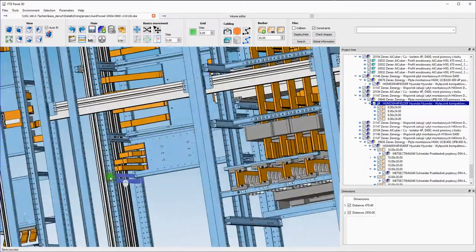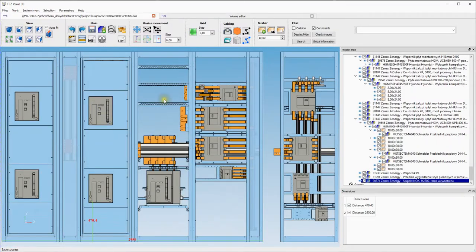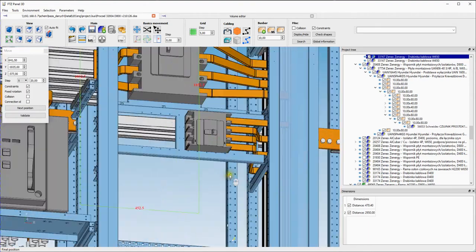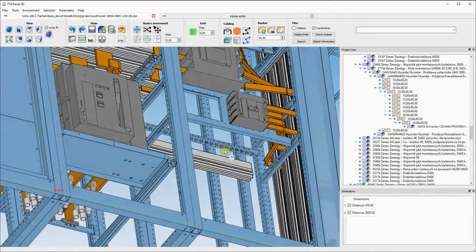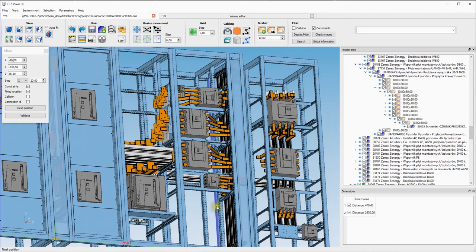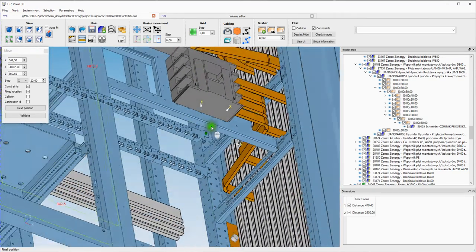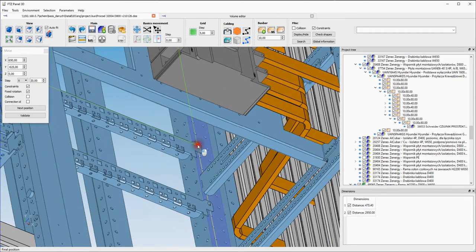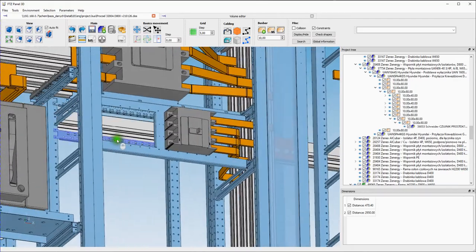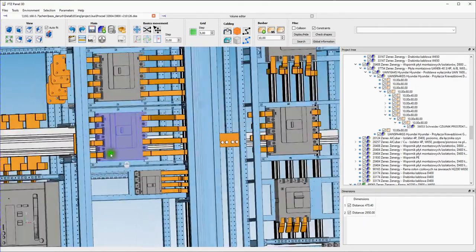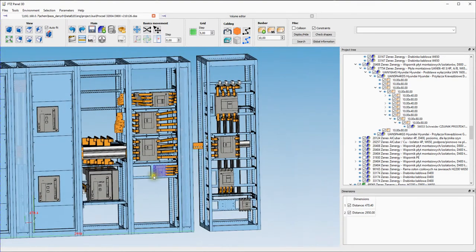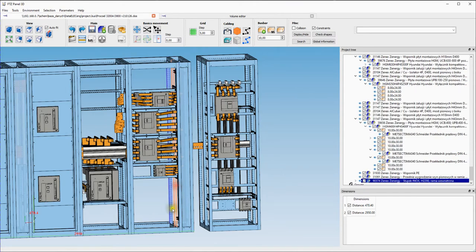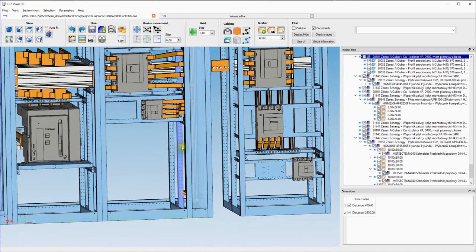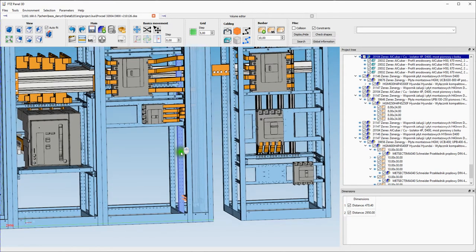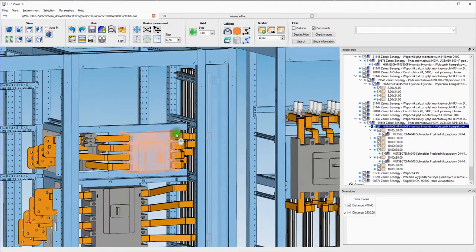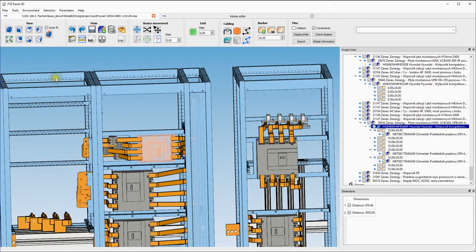But somewhere to the back side maybe I will also add cable ladders here. Let's say somewhere here we will add a cable ladder, so you can add a current transformer. Yeah, here you can install a current transformer for the earth leakage and go out with those cables up or down, whatever. This solution is nice because you have a lot of space for new breakers here, or regular circuit breakers. On the top there is also some small space for a breaker like 250 amperes, and outgoing by cables here.